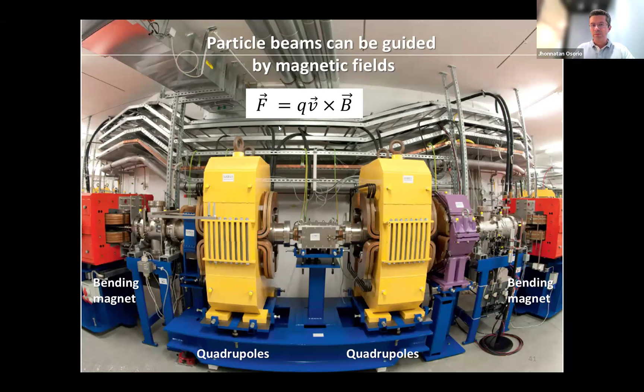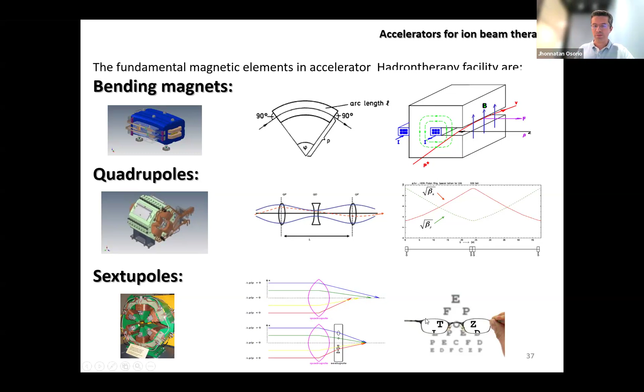Then once you're able to accelerate the beam inside of the accelerator, you need to control the beam, right? Therefore you need a really simple formula, the Lorentz formula. Inside of any particle therapy facility, you will always find roughly 3 or 4 kinds of magnets. We are talking about the Lorentz force, and you need a magnetic field in order to control the beam. There are the bending magnets, which control the trajectory of the beam. Then you have quadrupoles, a magnet with 4 poles, which control the dispersion of the beam, because you have a bunch of particles and they try to go up and try to escape. And you have sextupoles, which do a fine tuning of this spreading of the beam, some moment in dispersion.